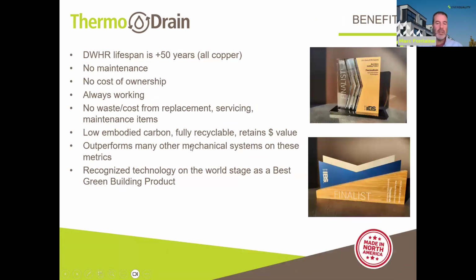So what's interesting about drain water heat recovery is that the construction is very robust. It's kind of a set-and-forget device. There's no maintenance to be done. It has a long life cycle. The cost of ownership is next to nothing. There's no commissioning during installation or maintenance down the road. So it's a very good device to install for the long term, where there's no degradation of performance, and no degradation of performance based on lack of maintenance and whatnot.